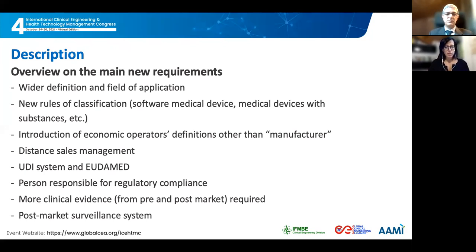The medical device regulation widens the definition of medical devices and also has a wider field of application. It also gives new rules of classification. For instance, with respect to the medical device directives, it adds new rules of classification for software medical devices and medical devices with substances. It introduces the definitions of new economic operators, such as distributors and importers, that the directives didn't define. It also manages distance sales, and it introduces the UDI system, the unique device identification, as you already probably know.